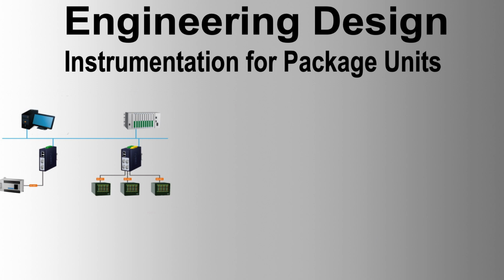Specification for package units. Limits of supply. The vendor shall provide junction boxes, electrical connections, and air supply connections at the battery limit of the skid to provide an interface for the principal's cabling and instrument air supply. The contractor shall be responsible for the interface between the equipment package and the rest of the plant.